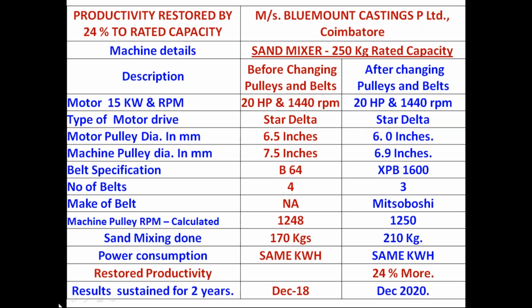This has happened on a production machine, a sand mixer. After replacing the pulleys and belts, they were able to achieve almost 20% increase in production. That is not really an increase in production; the production is restored to the capacity of the given machine. It is a sand mixer where the mixing of sand has to be homogeneous. The old machine, they were trying to replace it. It would cost more than 10 lakhs. They just spent only 10,000 rupees, and achieved the same motor machine capacity, almost 20%. They were able to restore the machine capacity. It can happen in any of your energy audits, wherever you go to belt coupled machines. This is a low hanging fruit for the energy auditor. Next, please.